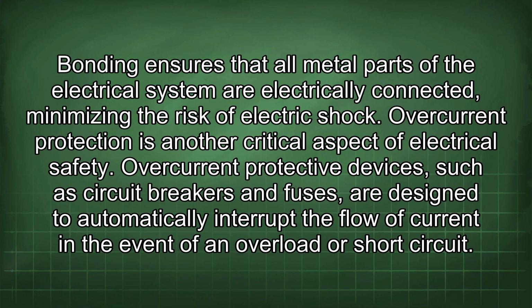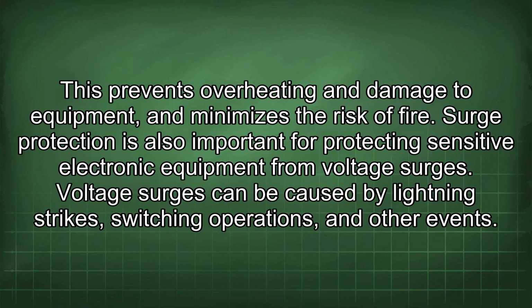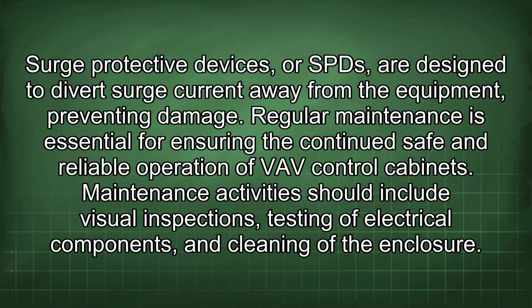Overcurrent protection is another critical aspect of electrical safety. Overcurrent protective devices, such as circuit breakers and fuses, are designed to automatically interrupt the flow of current in the event of an overload or short circuit. This prevents overheating and damage to equipment and minimizes the risk of fire. Surge protection is also important for protecting sensitive electronic equipment from voltage surges. Voltage surges can be caused by lightning strikes, switching operations, and other events. Surge protective devices, or SPDs, are designed to divert surge current away from the equipment, preventing damage.